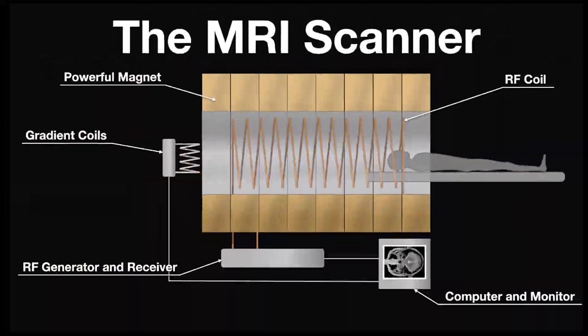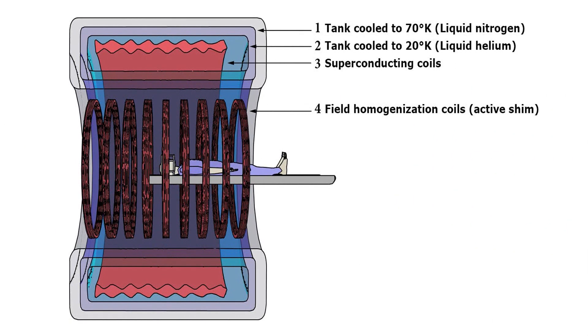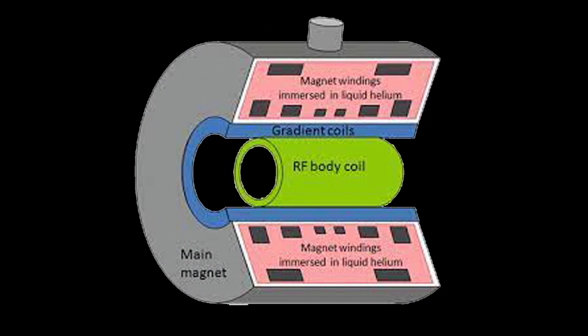Why does the MRI system need a chiller? All MRI scanners contain superconductive magnetic coils. These coils must be cooled to approximately minus 269 degrees Celsius to promote superconducting properties in the metal alloys. This low cooling temperature is achieved by circulating liquid helium around the magnetic coils.